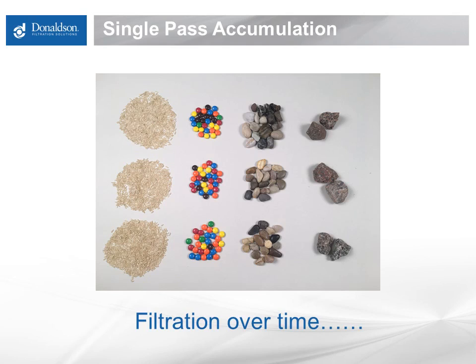Anyone giving a firm, confident answer about real-world fuel filter life may not understand how difficult that answer really is to predict, or is touting a filter so open that it is doing very little work and will last darn near forever, no matter what fuel is coming to it. When I am asked how long a filter will last, I talk about the state of the fuel today and that based on normal conditions, we can make some assumptions for planning, but to say with certainty how long a filter will last — that's just something I can't do. Because sometimes, and more frequently now than ever, something unexpected happens in the fuel.